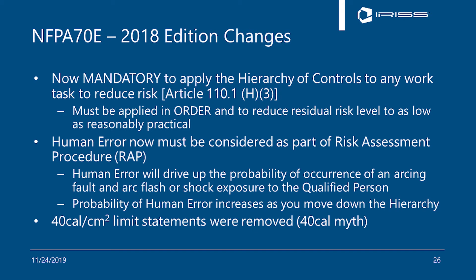And essentially the rule is do the first one first. If you can't do that for some reason, then and only then can you move to the second. If you can't do that, then and only then can you move to the third, and so on down the list, right? So it must be followed sequentially. First one is, can I do this task de-energized? That's the question you ask yourself. Can I perform this maintenance task de-energized? If the answer is yes, then that's what you do. Stop. Don't go any further down the list. Do it de-energized. Take the shutdown, even if it's inconvenient, find a way, do it de-energized.